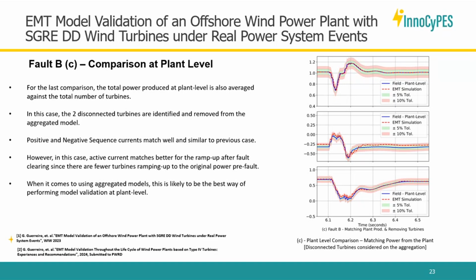Now we see that the reactive power is within the tolerance. We're slightly off, but still within the tolerance. And we see that the reactive power, especially on the ramp up, matches pretty well. So we use this model for something else. Just keep in mind that this has been validated as well for operation.